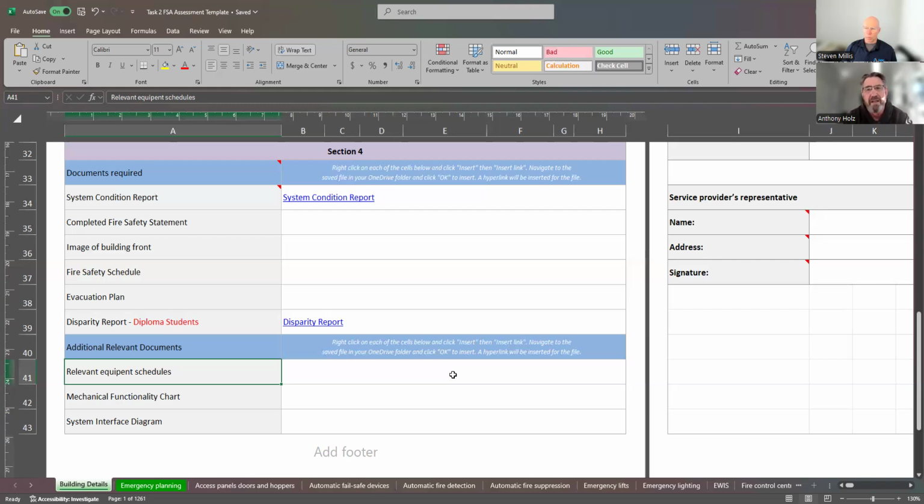Yeah. Look, I've done it myself. I've been here and done that. I've missed assets in buildings because I just didn't have access to that particular area when I first walked around. Yeah. And the buildings also get modified over time. So if you're coming in 20 years after construction, you may not be aware of modifications that the building owners made without DAs, or moved internal walls and knocked walls out. So yeah, it's moving away from just inspecting what's there to verifying what should be there.